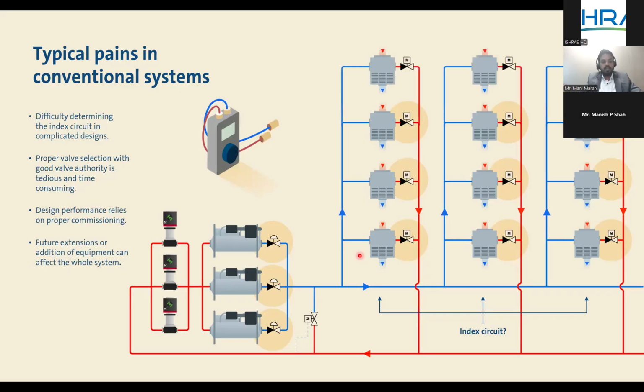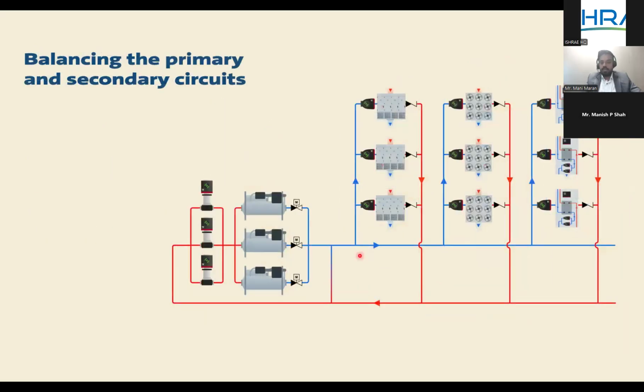And further extension, the conventional system has to, let's say if the load has to be added at a later stage, if we design the pumping system, the pumping head has to be designed for the future expansion as well at the first step itself. So that is the challenge in terms of design aspects when you add a load at a further stage. So we are addressing those challenges with distributed pumping or coil pumping or decentralization of pumping.